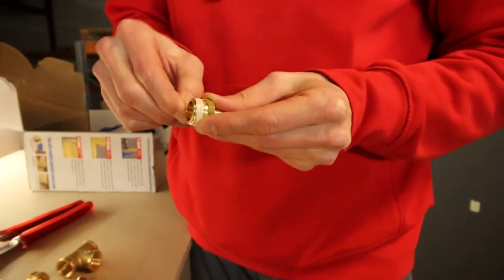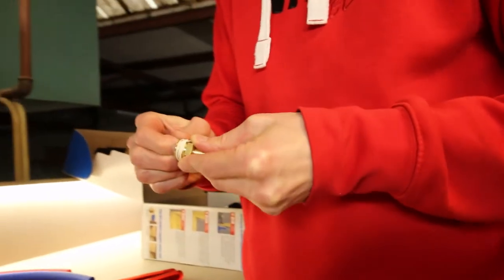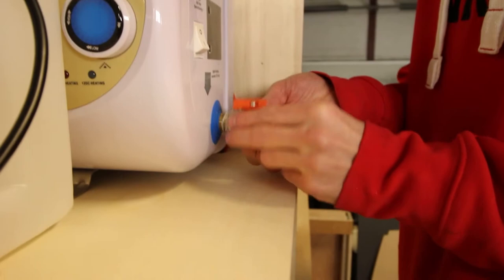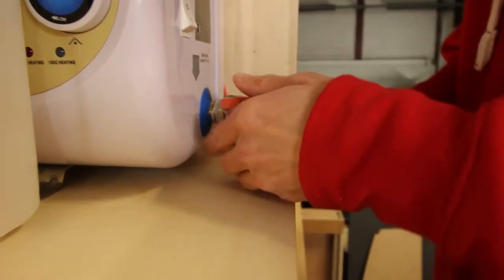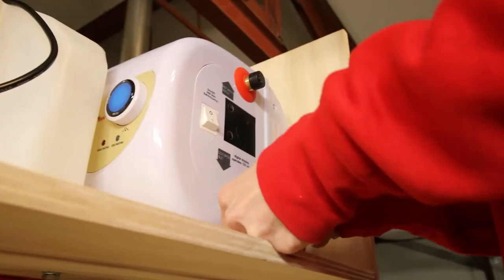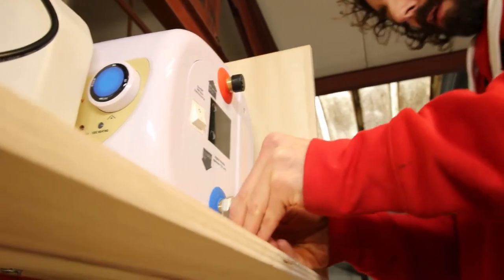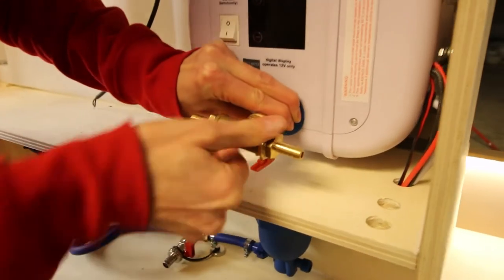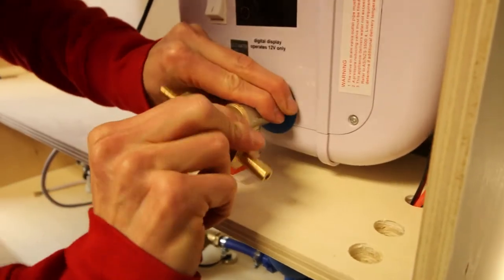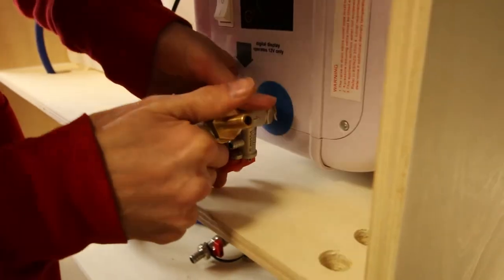The screw connections are wrapped with Loctite 55 thread sealant to make it watertight. The pressure relief valve with a non-return valve is mounted on the cold water inlet. Then the T-piece with the two hose tails is screwed onto it so that the hoses can be connected.